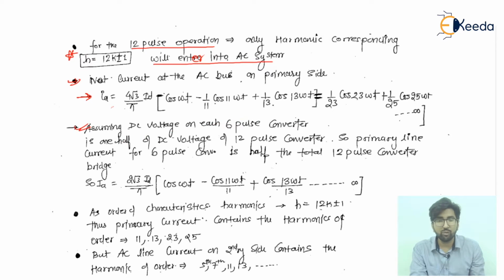Now let us assume the DC voltage on each 6 pulse converter. So I can say that will be 1/2 of the DC voltage of the 12 pulse converter, yes or no? So the primary line current for the 6 pulse converter will be 1/2 of the total 12 pulse converter bridge. So likewise it is going to happen. Please read it carefully because it is important here.